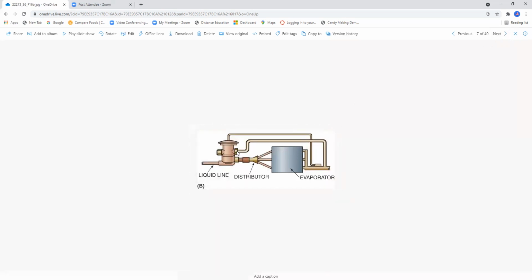Okay, here we have a TXV. Notice that we have a liquid line going in. We have the thermal bulb, which is mounted on the outlet horizontal plane of the suction line. This is the equalizer connection, which is also mounted next to the bulb location. And here we have a distributor, and then we have these circuits. In this case, we have 3 circuits on this evaporator coil. The one I worked on today in West Covina had 6, and circuit number 6 developed a leak on the capillary line because that line was submerged in the condensate tray. So just be aware of that.